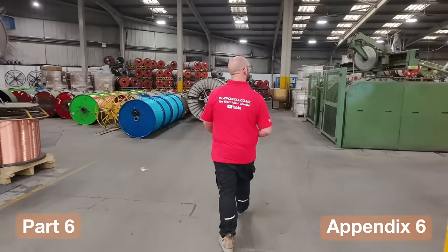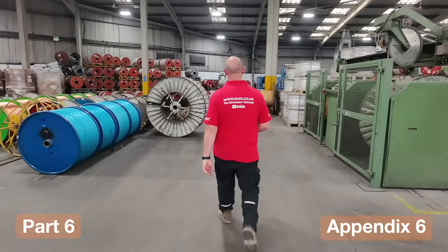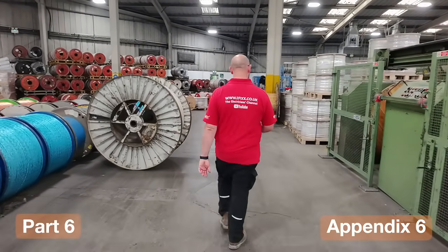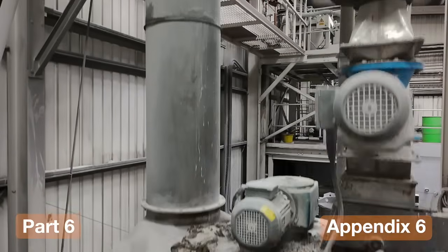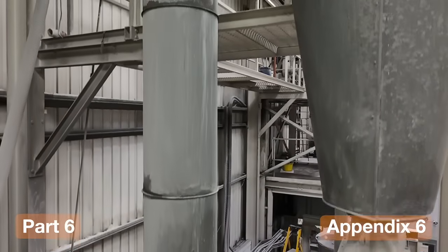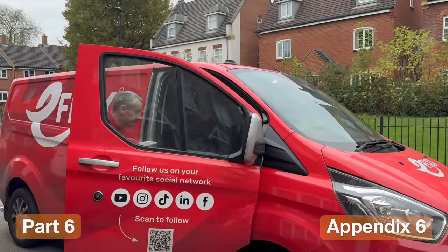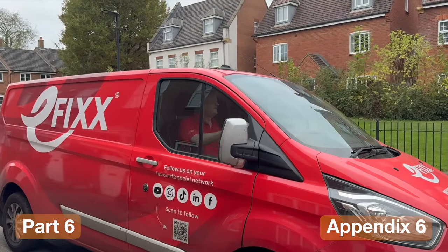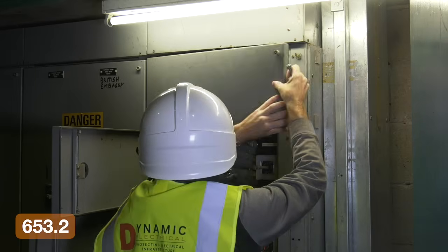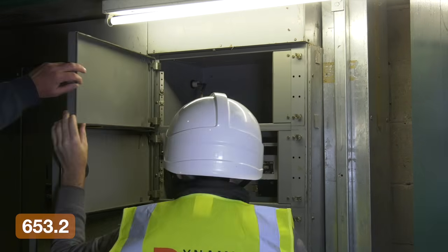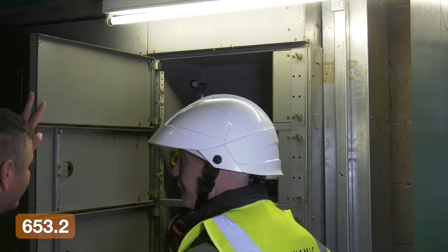The extent of the installation and any limitations must now be agreed before the inspection begins. So if parts of the installation cannot be accessed or assessed, that is defined up front. FI is then used where the limitation prevents a proper assessment. So it is no longer a fallback, it is linked directly to scope and access. There is also a shift towards evidence. Regulation 653.2 now allows photographic and thermographic images to be included in the report.